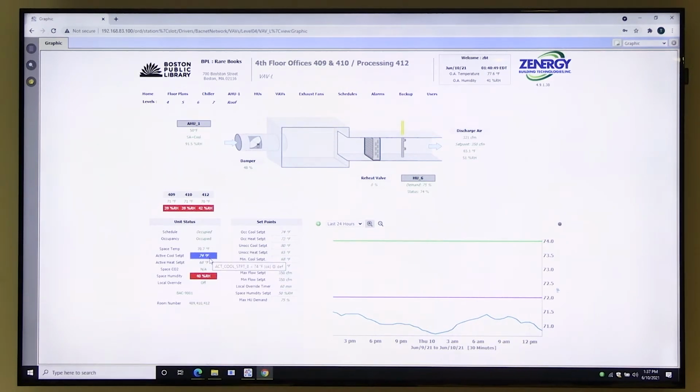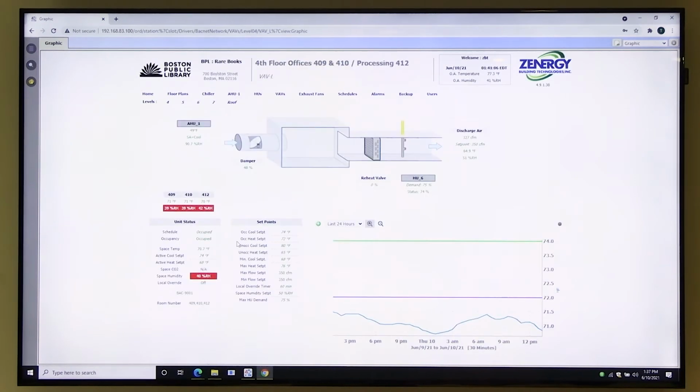That is the active set point, what it's looking at right now. If you wanted to, say, change the set point forever and have it always be 68, you would come over here to the default set points. So if I were to come here and set this to 70, now that's going to update to 70, and that should push your active to 70 currently right now. And you could always, if you actually want it to be 69 right now, you can do that. So those are kind of your heating and cooling set points.